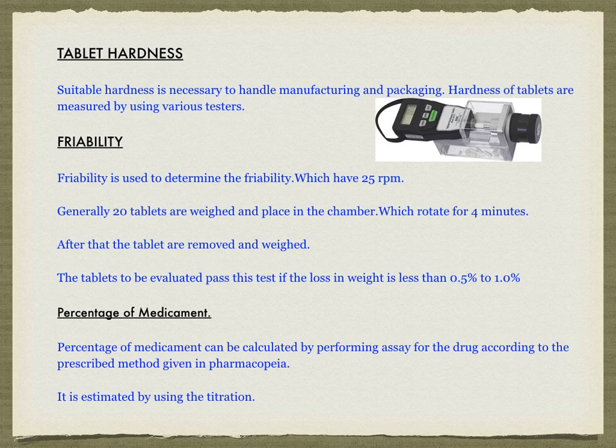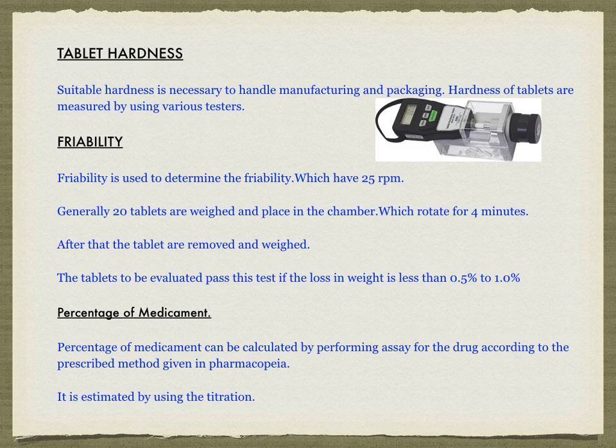Friability testing is used to determine the friability of tablets, with the apparatus rotating at 25 RPM. Generally, 20 tablets are weighed and placed in the chamber which rotates for 4 minutes. After rotation, the tablets are removed and weighed. Tablets pass this test if the loss in weight is less than 0.5%.